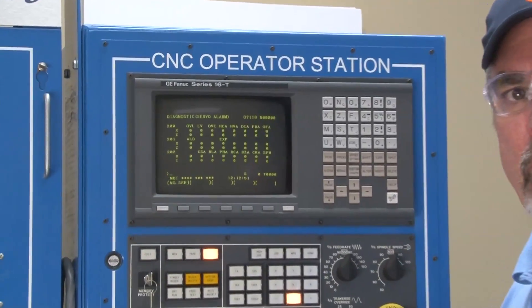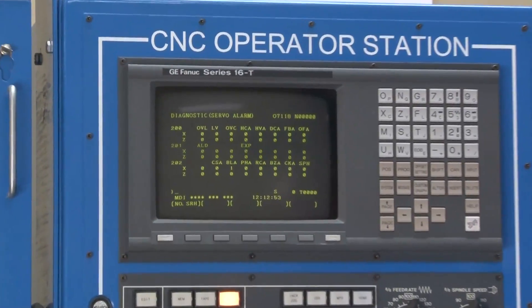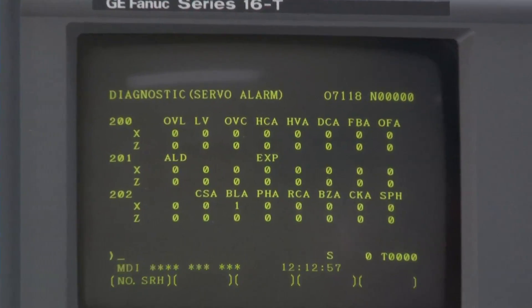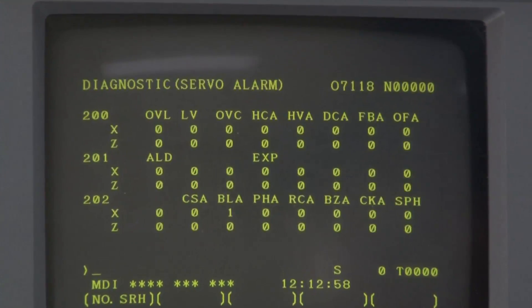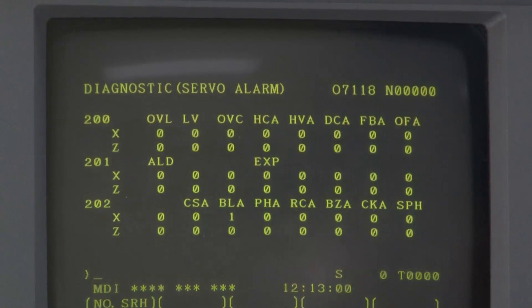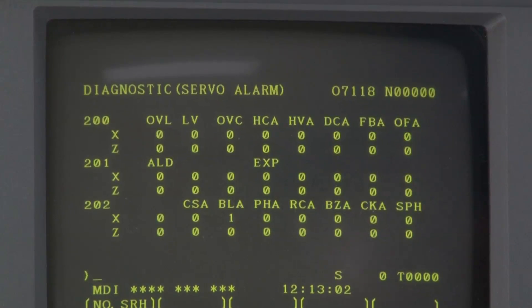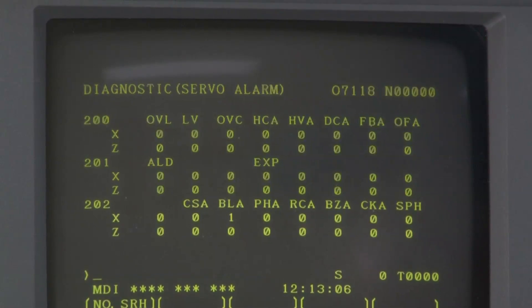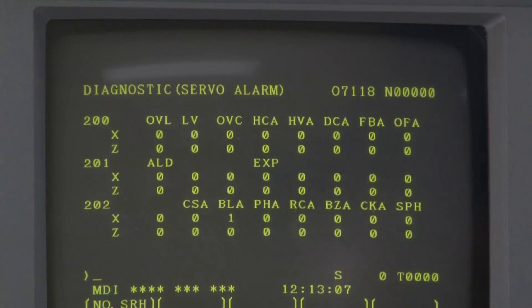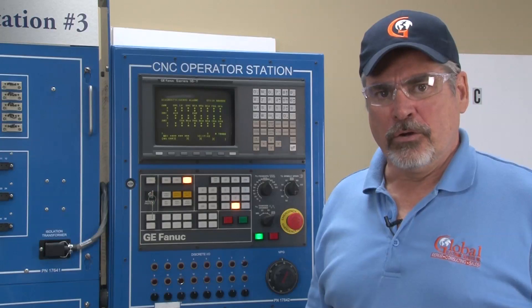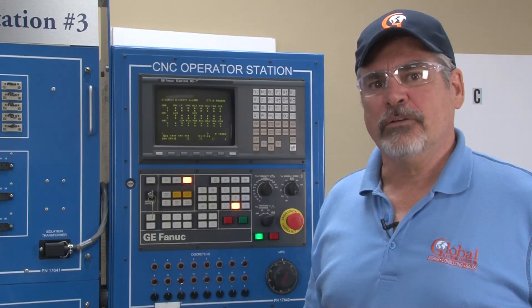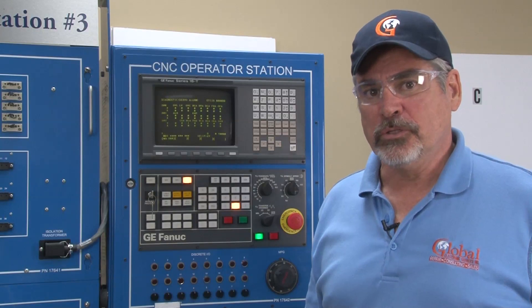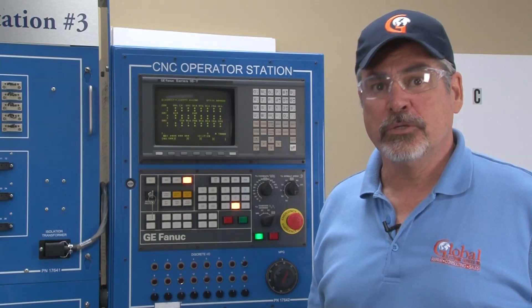The servo drive monitors the quality of the current passing through it. If it sees noise inside of the system, it will generate a high current alarm and shut the machine down. An over current alarm indicates that too much current has flowed through the DC link, and is usually caused by a short in the system. High current alarms can be caused by a defective servo drive or, more commonly, coolant contamination inside of the motor windings or cable.